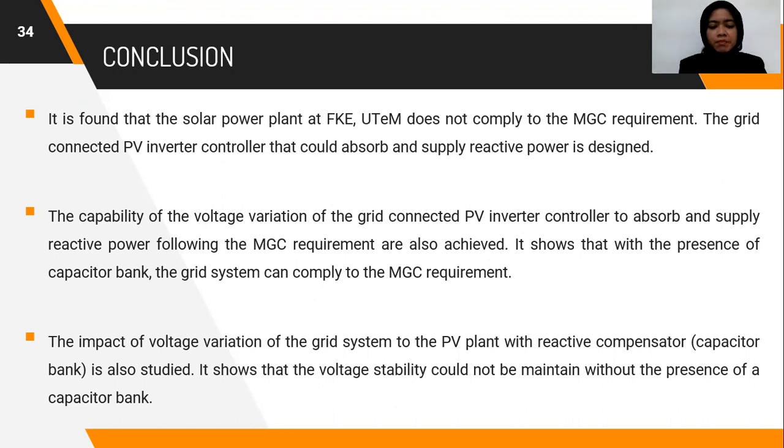And lastly, the impact of voltage variation of the grid system to the PV plant with reactive compensator, which is the capacitor bank, is also studied. It shows that the voltage stability could not be maintained without the presence of a capacitor bank.